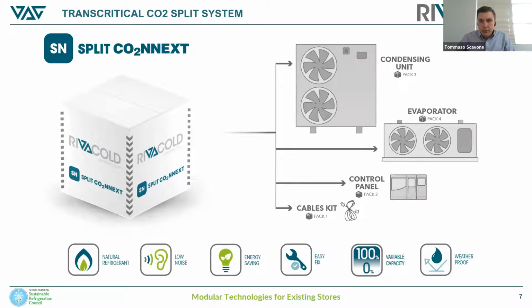For walk-ins instead, we are offering the complete split system, or the SN range, that comes as an all-in-one package ready to be installed and giving big advantages in terms of cost and time saving to both the end user and the installer. This solution is perfect when you are adding a new walk-in to an existing store, obviously in case of retrofitting an old HFC system, but especially convenient when you want to keep the walk-ins independent from a central remote system, so allowing modularity, flexibility, and also redundancy in case of failures.